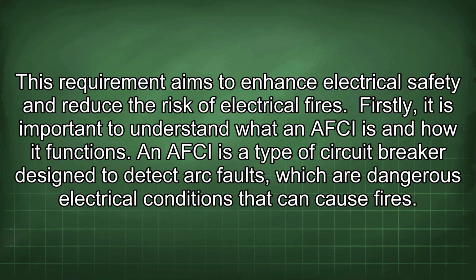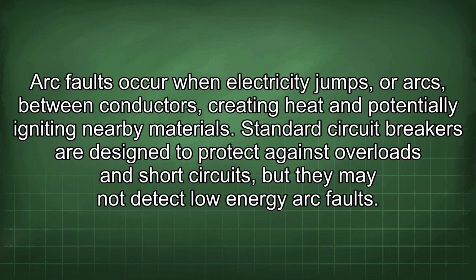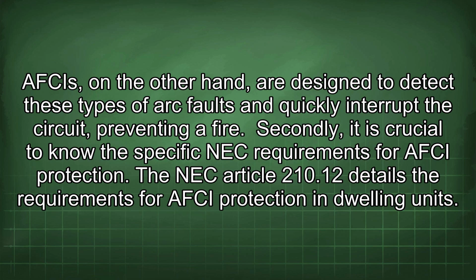Firstly, it is important to understand what an AFCI is and how it functions. An AFCI is a type of circuit breaker designed to detect arc faults, which are dangerous electrical conditions that can cause fires. Arc faults occur when electricity jumps, or arcs, between conductors, creating heat and potentially igniting nearby materials. Standard circuit breakers are designed to protect against overloads and short circuits, but they may not detect low-energy arc faults. AFCIs, on the other hand, are designed to detect these types of arc faults and quickly interrupt the circuit, preventing a fire.